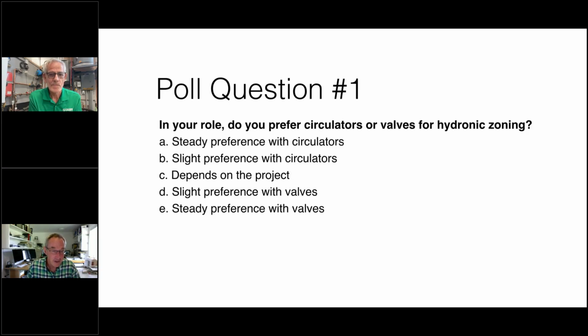Honestly, I'd have to say it's probably almost a 50-50. I would agree with that. And I've seen guys go one way and the other, then they go back to the previous choice. They zoned out with circulators always, then they tried zone valves for a while. And now with these new ECM pumps that can do so much more controllability, they're going back to pumps. But obviously zone valve is a better way.